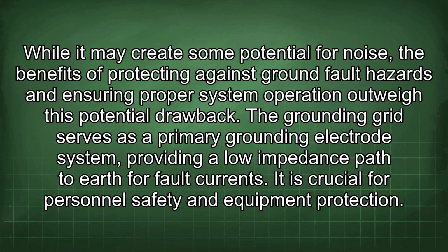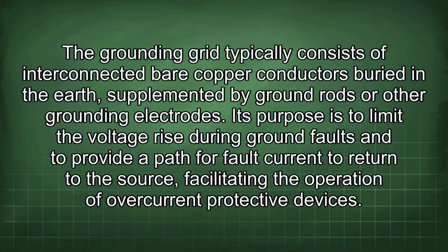The grounding grid serves as a primary grounding electrode system, providing a low-impedance path to earth for fault currents. It is crucial for personnel safety and equipment protection. The grounding grid typically consists of interconnected bare copper conductors buried in the earth, supplemented by ground rods or other grounding electrodes. Its purpose is to limit the voltage rise during ground faults and to provide a path for fault current to return to the source, facilitating the operation of overcurrent protective devices.